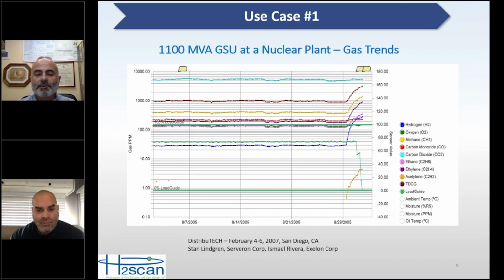The blue line is hydrogen. And if you'll note, this is on a logarithmic scale, so you can see what's going on around 1 ppm as well as what's going on around 1000 ppm. What you see here is early in the month, all the lines were flat. And as I said, if you're watching an online monitor and it's showing that the gas levels are consistent, that means no new gas is being generated. There's not an active fault or an active problem in the transformer. Once your gases start increasing, that's the time for concern. And this, of course, was an 8-gas monitor on a very critical transformer, so it's easy to justify that.